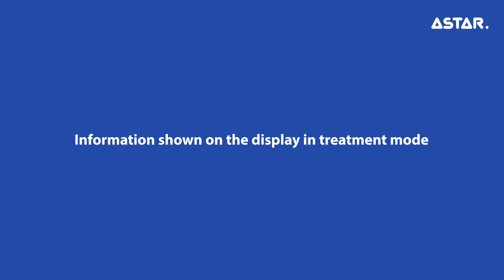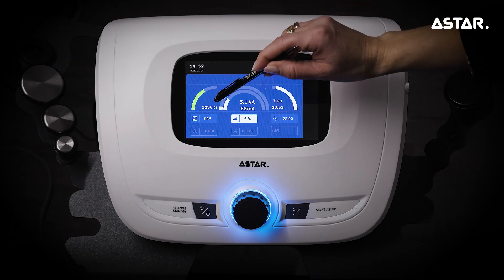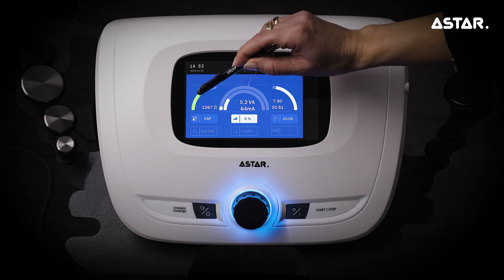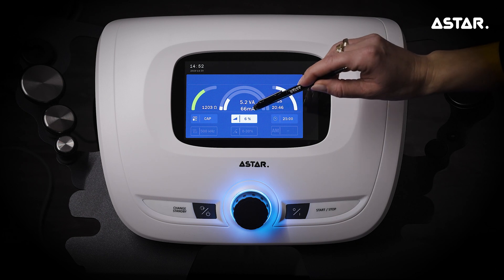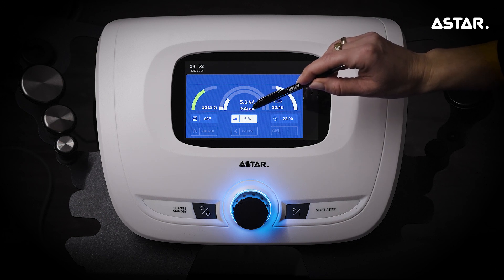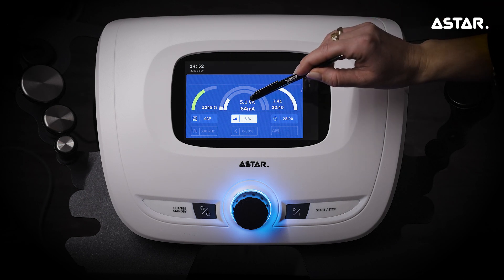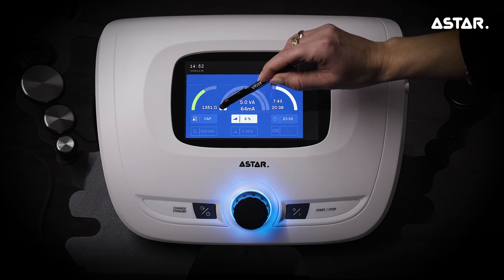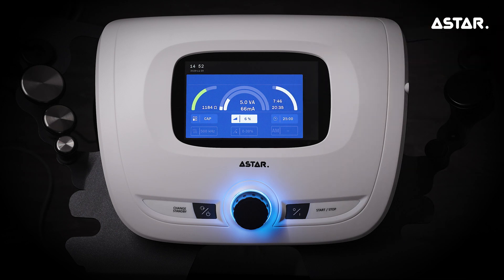Information shown on the display in treatment mode: Patient's impedance — the better the contact between the electrode and the patient's body, the more filled the indicator is. Current delivered to the patient at a particular time, value given in mA. Power delivered to the patient at a particular time — the more power is delivered, the more filled the indicator is.